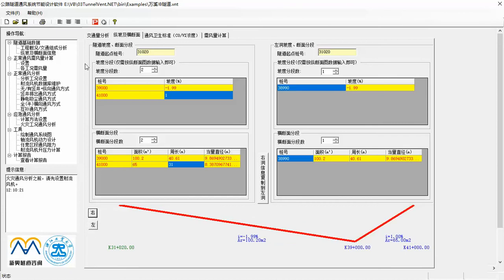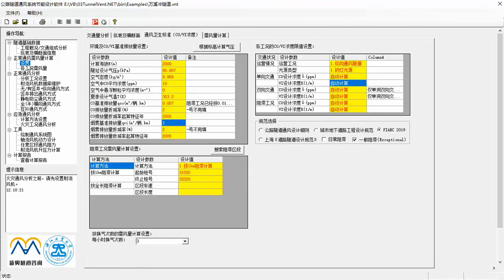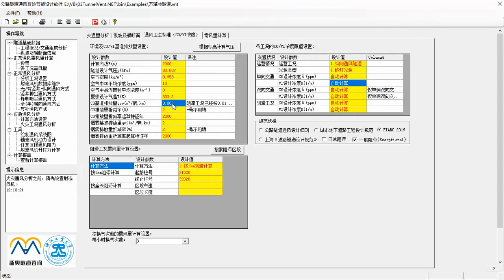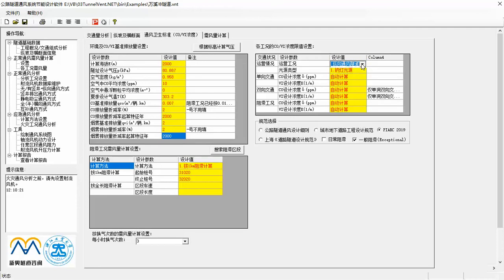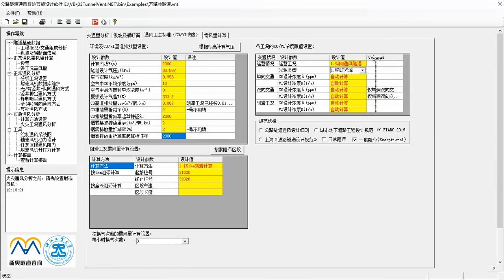The second step is to calculate air demand. First, you should set some parameters in this tab. In the first table, you can set elevation value, environment pressure, air mass, background CO and VI concentration, reference emission value, discounting rate and its reference year. Then in the second table, you can set the target or design concentration value for CO and VI in different operation conditions. For example, different ventilation modes including longitudinal and transverse ventilation mode, lighting modes including LED or HPS.